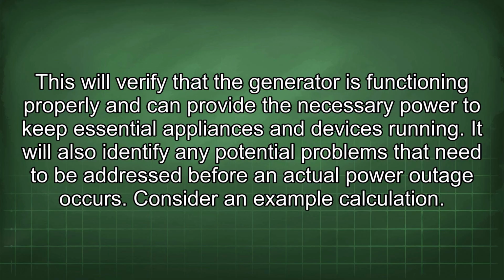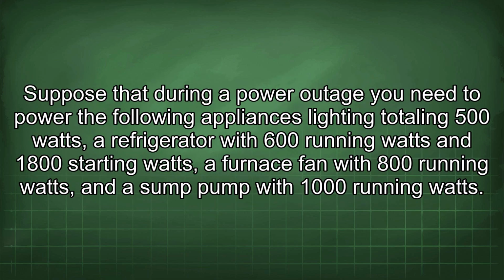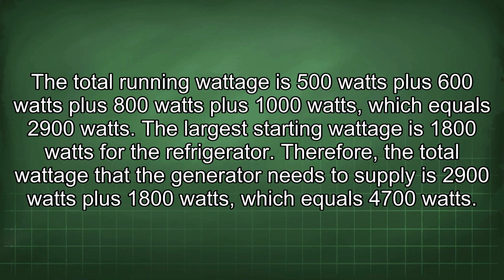Consider an example calculation. Suppose that during a power outage you need to power the following appliances: lighting totaling 500 watts, a refrigerator with 600 running watts and 1800 starting watts, a furnace fan with 800 running watts, and a sump pump with 1000 running watts. The total running wattage is 500 watts plus 600 watts plus 800 watts plus 1000 watts, which equals 2900 watts. The largest starting wattage is 1800 watts for the refrigerator. Therefore, the total wattage that the generator needs to supply is 2900 watts plus 1800 watts, which equals 4700 watts.